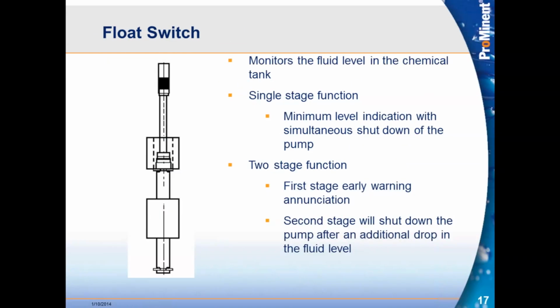Okay. We also have level switches. In this case, it's a two-stage. We also have some single stage for some of the other pumps. But a two-stage level switch, you'll see at the very bottom that rectangle is the float. So we would suspend that so that it's just above the foot valve.